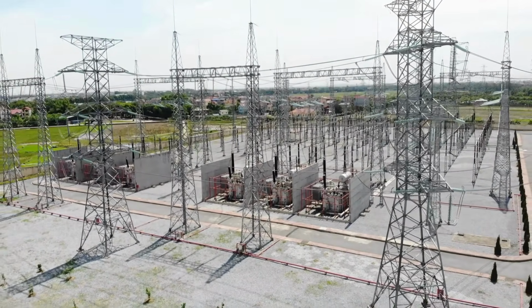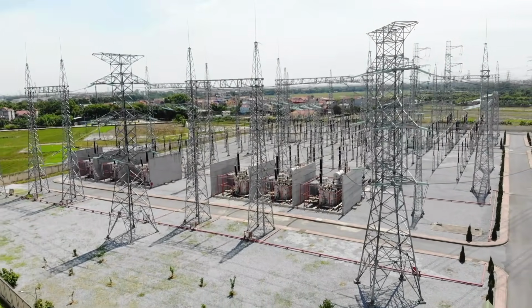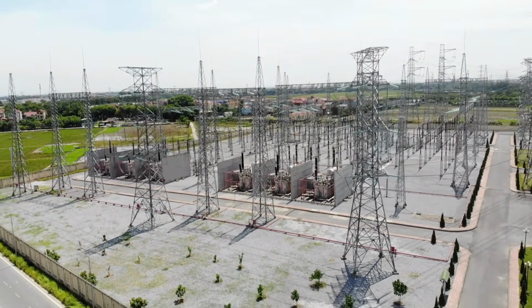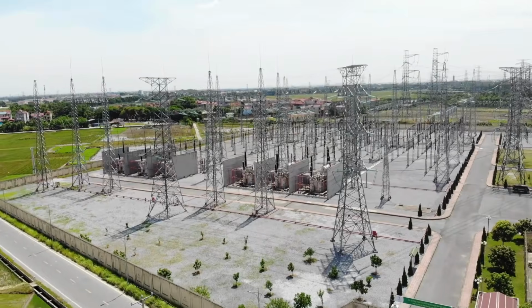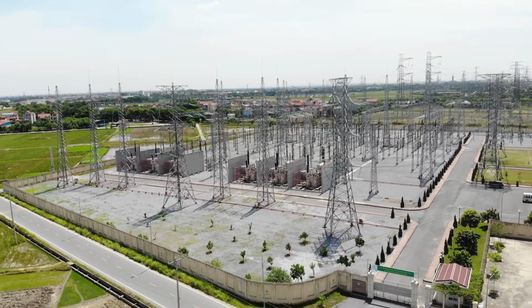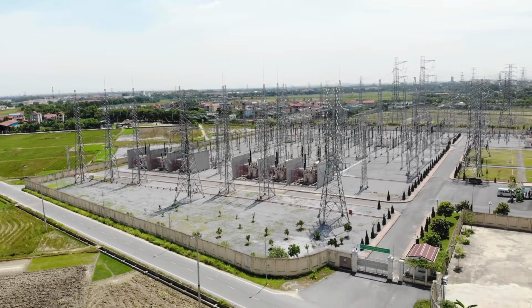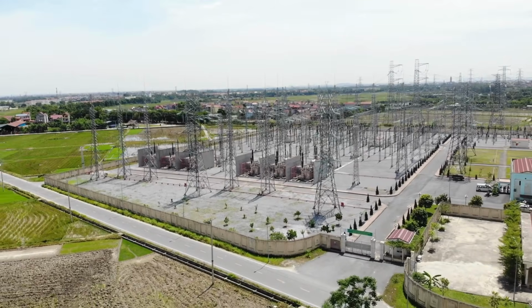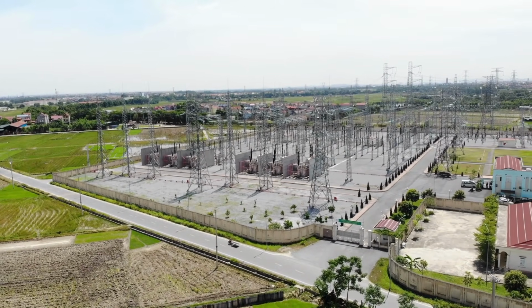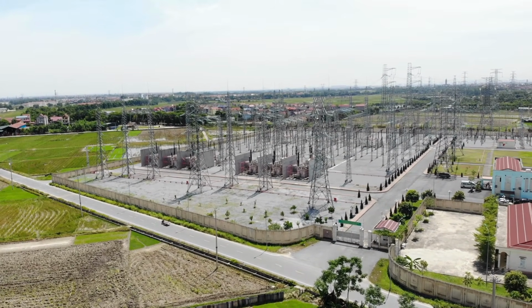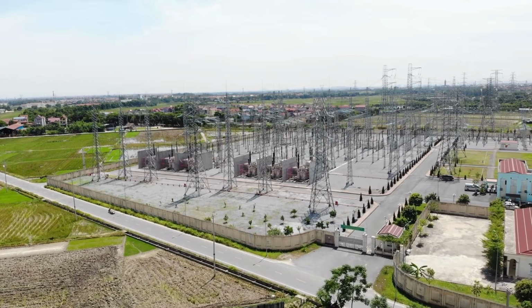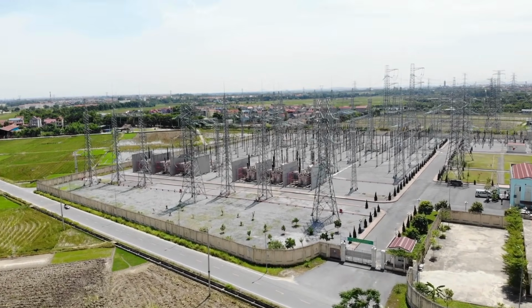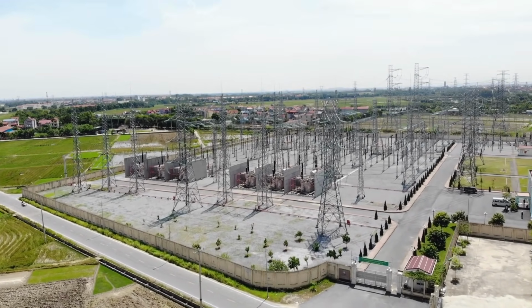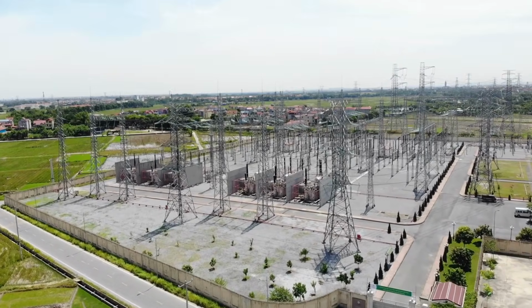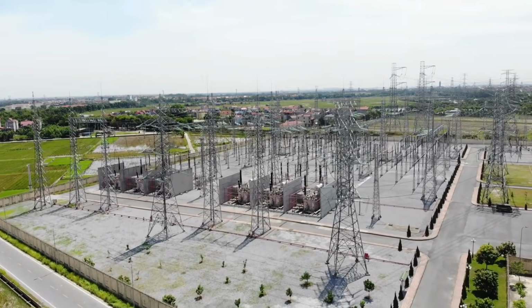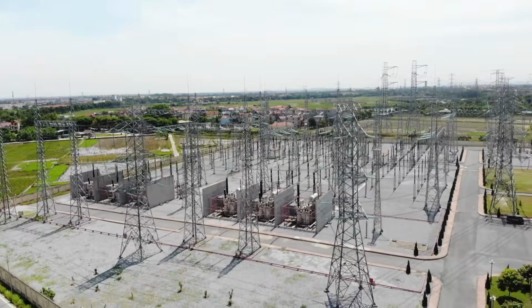Instead of fighting this problem, engineers use a completely different approach: high voltage direct current, or HVDC. Here's how it works. The generator still produces AC; nothing changes inside the powerhouse. But after the step-up transformer, electricity enters a converter station. Here, power electronics convert AC into DC. The DC voltage may reach plus-minus 500 kilovolts, plus-minus 800 kilovolts, or even 1100 kilovolts.